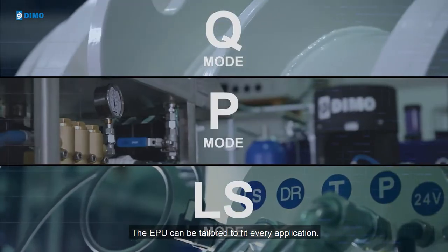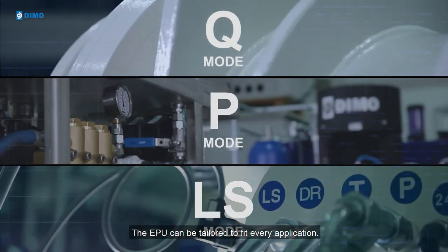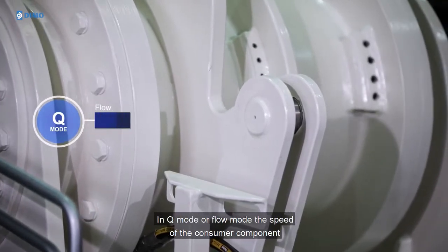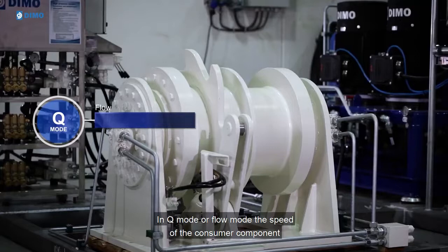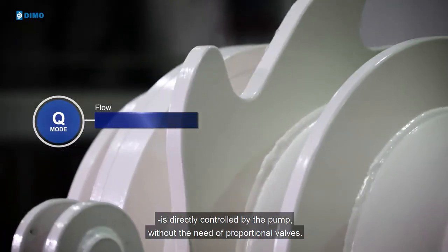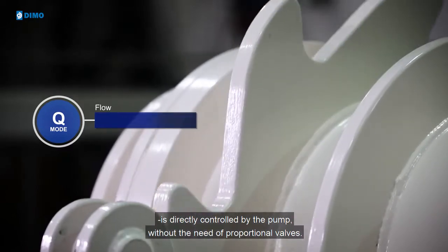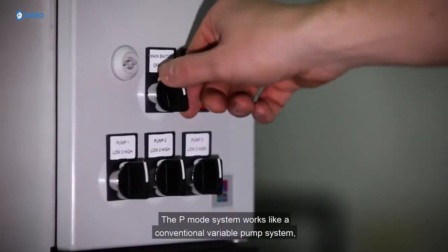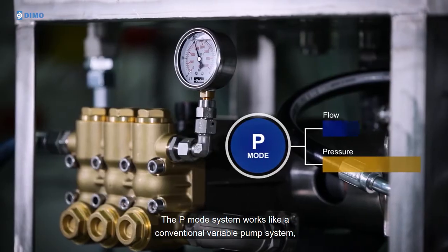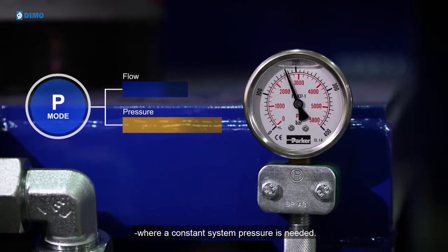The EPU can be tailored to fit every application. In Q mode or Flow mode, the speed of the consumer component is directly controlled by the pump, without the need of proportional valves. The P mode system works like a conventional variable pump system, where constant system pressure is needed.